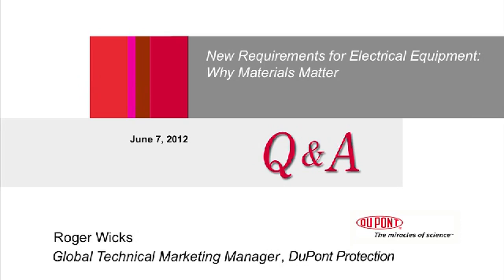I'd say the stiffness of the kraft papers might be on a par. There's different types. There's a whole range of kraft papers, and so we'd have to look at the very specific type of kraft paper to know the relative stiffness versus that paper. But I'd say they're pretty similar. NMN laminates tend to be somewhat stiffer than Nomex paper of an equal thickness. I would say, though, that if the application is for liquid-filled type transformers, an NMN type laminate probably shouldn't be considered because the polyester films have issues in those type of applications.